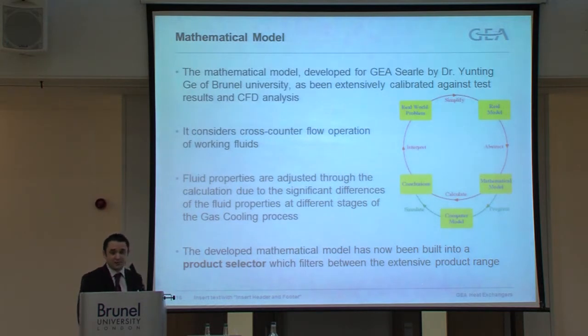The final aspect of the project was to develop this mathematical model to be used in the product selector, and this was developed by Dr. Yunting Ge and had been extensively calibrated against 18 months of capacity testing as well as CFD analysis. It considers a cross-counterflow operation of the working fluids. The fluid properties are also continuously adjusted as it's doing these calculations through an iterative process. Because the fluid's changing from 120 down to the mid-30 degrees, the properties of those fluids change considerably, and you need to consider that in the design of the heat exchanger.